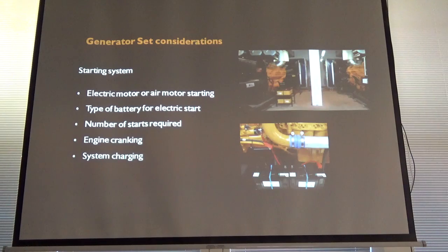You can have two sets of starters, you can have two sets of batteries and chargers. You can have them all sized for 6 starts, 3 starts, but either way the sets are so reliable these days. After 3 start attempts, irrespective of what capacity you've got in your batteries or transfer, changeover systems you've got, dual sets, I would say someone needs to go and manually investigate. It alarms and they have to clear it on the control panel of the generator itself, because something's wrong for that set not to start at 3 attempts. You'll have a 10-second crank and you'll have a 10-second dwell before it will then start again. The reason why is that those starter motors get hot, and you don't want to burn them out.